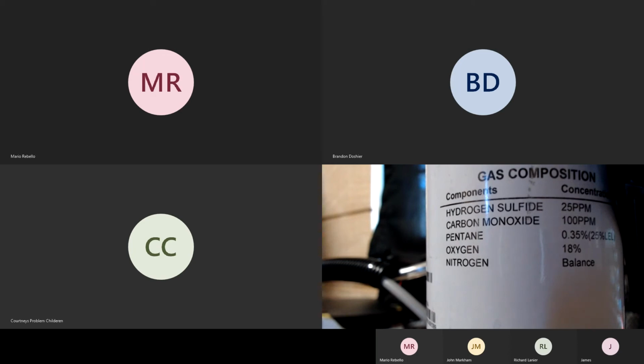Calibrations should be done once a month. And the docking stations will just automatically tell it to do it once a month whenever it's needed. And that's due to accuracy of the instruments. Bump testing, okay, is a little different. Bump testing should be done before each day's use, okay? And what that's doing is that's just telling us, hey, the instrument is responding to gas, the alarms are working. It's just a functionality test. That's all it is. It's not accuracy.